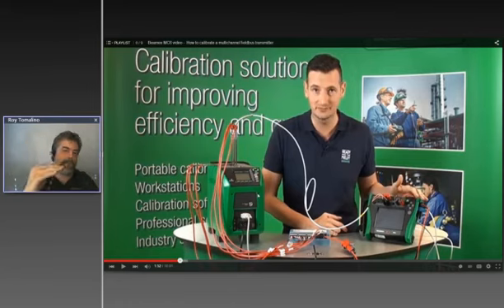Then we increase the temperature in the dry block to our next test point and grab the temperatures all the way around until we've achieved our second test point for all the probes. Now, because this is field bus, it automatically pulls out the process variable into the calibrator. If you were doing a multi-channel with HART, you would have to swap the leads for each temperature probe. There is a company that does create this all automated, so that is a possibility.